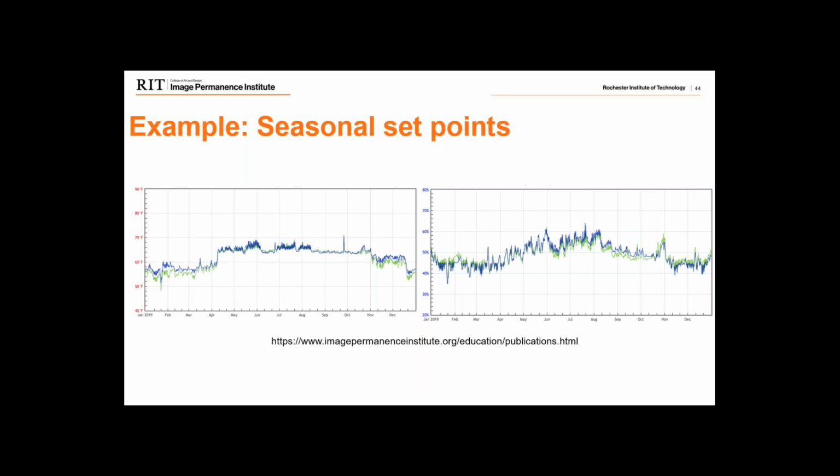So, for example, with the temperature, in the winter we're maintaining about a 55-degree temperature, and then in the summer we allow that to go up to a 65-degree set point. So in the winter, we're definitely getting some more gains. We're slowing down those rates of chemical decay, but we're still preventing the extreme temperatures in the summer.